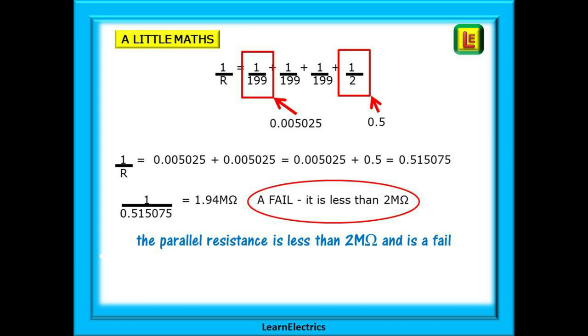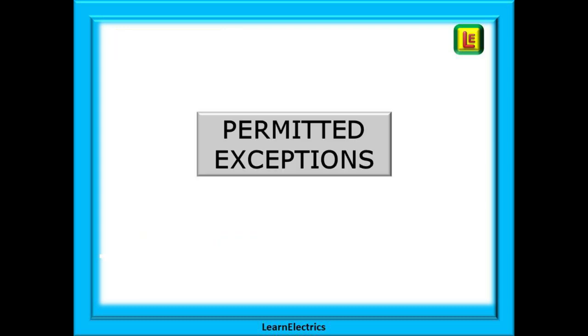Our parallel resistance is 1.94 megaohms. This is less than two megaohms and so the installation as a whole is a fail. Further investigation is required. Why is this last circuit so low? Is there a problem? Does it need rewiring? The more that you practice these calculations, the easier it becomes. There are some permitted exceptions to testing, but we shouldn't use a permitted exception just because we are lazy and want to shortcut the testing. If we can do the test, we should do the test.